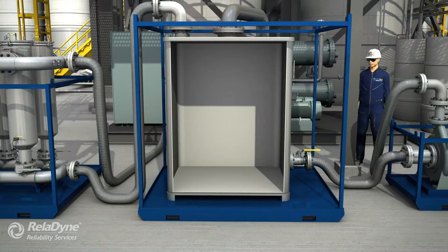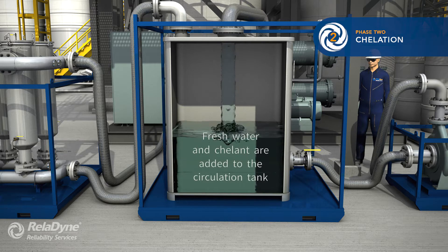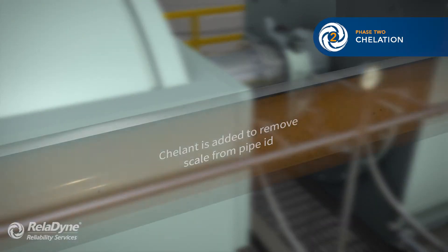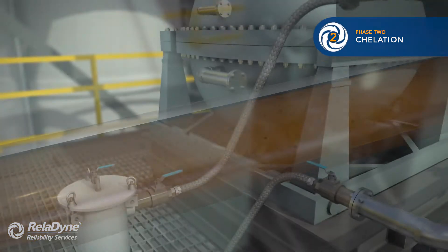After the predetermined degreaser circulation time is complete, we begin the chelation phase of the chemical cleaning. Chelant is added to the circulation mixture tank. This solution is circulated throughout the flush circuit to remove scale, rust, and other contaminants from the pipe wall.